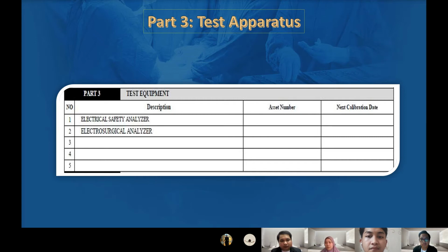For this PPM, the test equipment needed are an electrical safety analyzer and an electrosurgical analyzer. The asset number and calibration date can be found on the sticker behind or on top of the ESU.